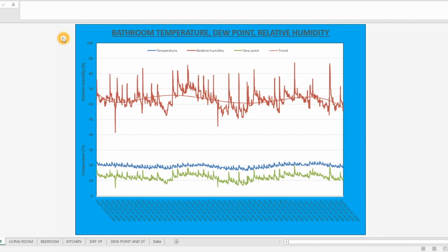So, in my opinion, these are best resolved by producing some decent data. Now, if you're looking at producing some decent data, you personally, in my opinion, need some data loggers in various rooms. You also need an external data logger for measuring vapor pressure outside as well, so you can convert that to see exactly what's going on with vapor pressure inside, so you look at the differential or the excess. You also really need surface temperature measurements in maybe a couple of places.